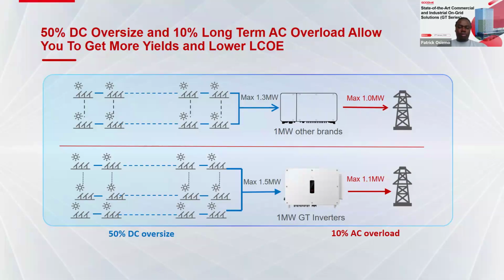How does this affect your plants? For the GT series, if you oversize by 50%, most of the time you'll be generating up to 10% additional on the AC output. So 1.5 megawatt peak of PV panels hooked onto the GT series, which is 1 megawatt, you'll be getting 1.1 megawatt. Compare this to other competitors, where you'll get a constant output regardless of oversizing, your output will stay at 1 megawatt. So we have a 10% beneficial factor from the oversizing capacity the GT comes with.